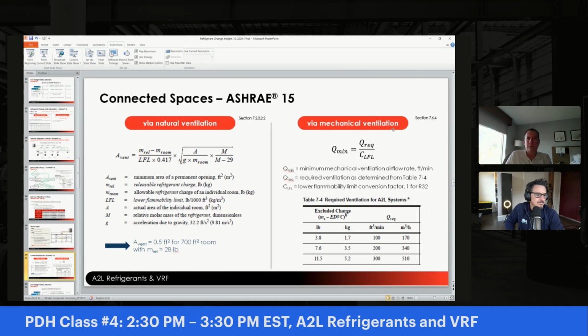So in this example here, we've got a 700 square foot room that has a system charge of 28 pounds. So this tells you that you could have an opening that needs to be about 0.55 square feet below 1 foot above the floor, which is kind of hard to wrap your brain around, but that is the wording. And if you do this, then you can count the neighboring space as part of your room volume. So again, more clarity, more choices, more flexibility.